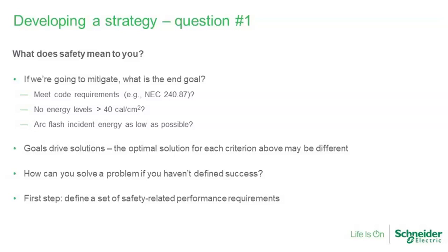Other folks say, I don't want anything more than 8 calories. Well, that may require a different set of solutions. Some that we've worked with say, I want my arc flash incident energy as low as possible throughout the facility. What may get you below 40 calories may not get you below 1.2, if that's what you're shooting for. Point being, whatever the goal, you can work towards getting there, but you need to define what those goals are. Goals drive solutions, and the optimal solution for each one of those criteria may be different. I don't think you can solve the problem if you haven't defined where you want to go, if you haven't defined success.